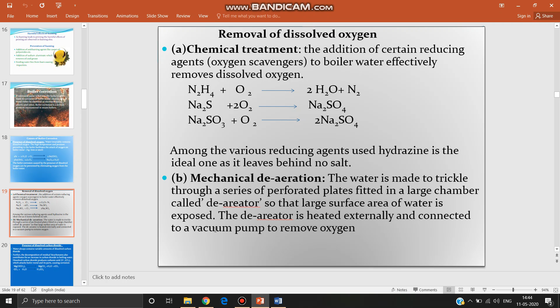The second method is mechanical deaeration. The water is made to trickle or sprinkle through a series of perforated plates fitted in a large chamber called a deaerator, so that a large surface area of water is exposed. But these perforated plates should be heated, then the removal of oxygen will be easier. The deaerator is heated externally and connected to a vacuum pump to remove oxygen. Simple process to remove dissolved oxygen.